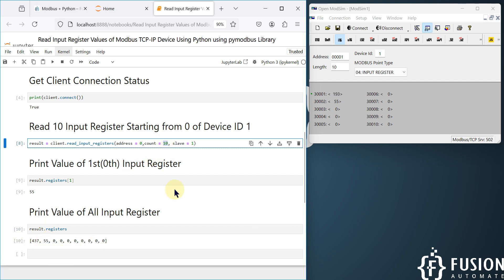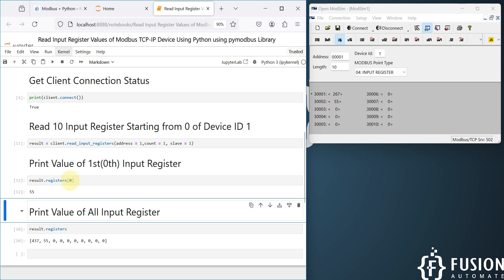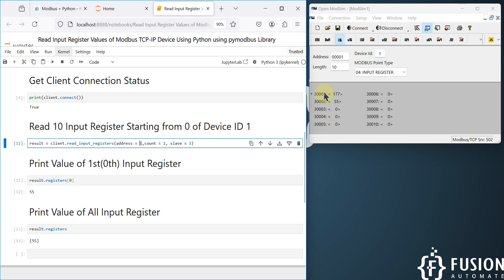If you want to read only one input register, set count to 1. For example, to read only the second input register (address 1), use starting address 1 and count 1, then access index 0 in the result. Register 300001 maps to index 0, and 300002 maps to index 1. Here, count is 1 so it reads only register 300002 on slave ID 1. The result shows 55, which confirms the read was successful.